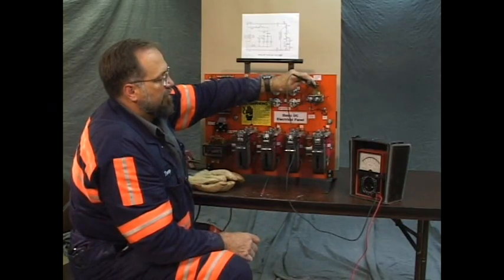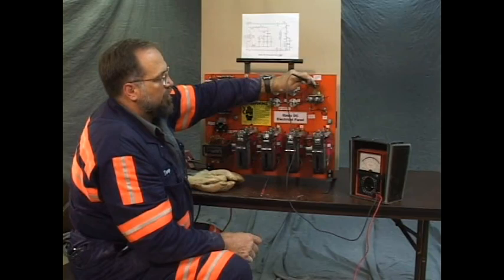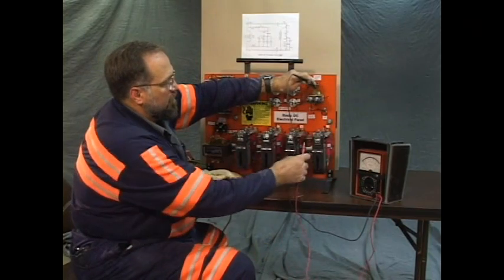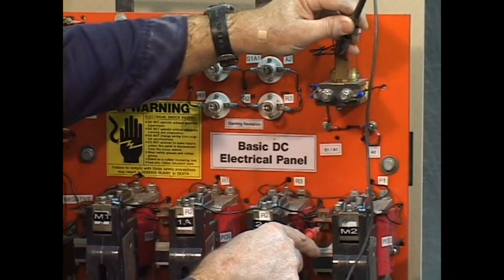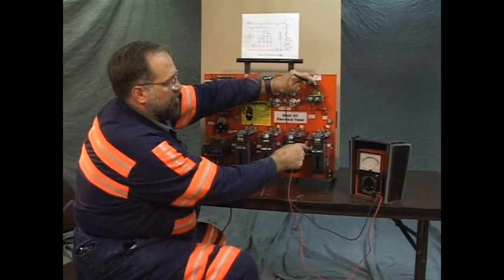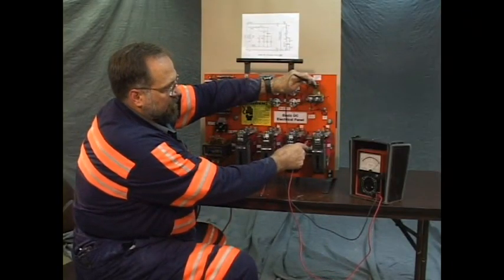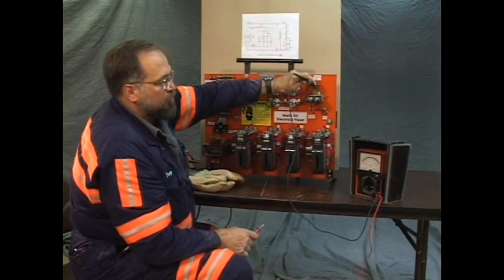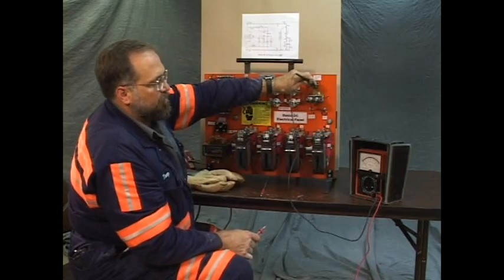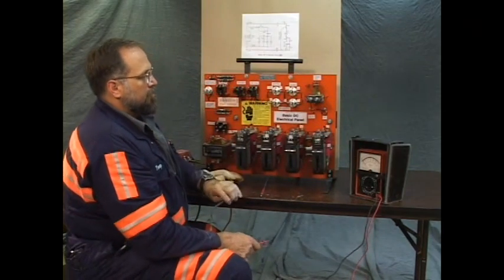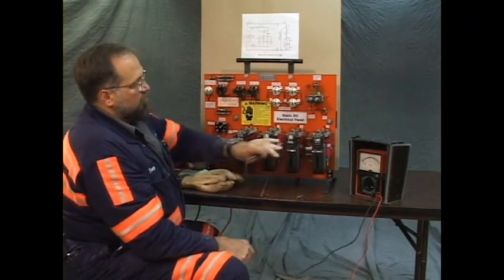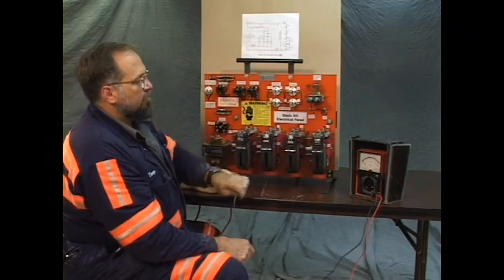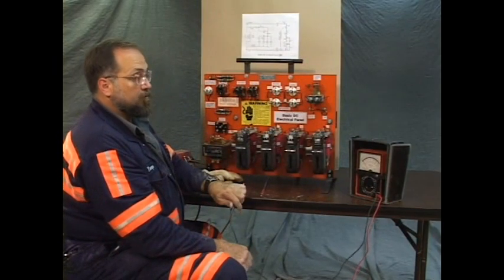Now to check the device, the print illustrates it as normally open, timed, closed. So this should be open, should be no circuit. But indeed we have a circuit. The component has failed, it's shorted, as a short circuit. It shows continuity through the timing circuit when it should not have it.